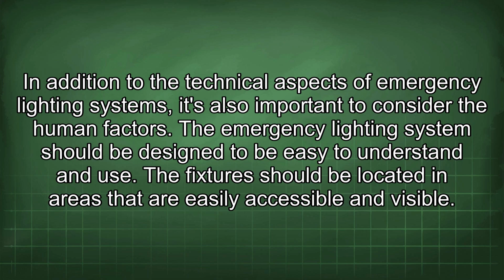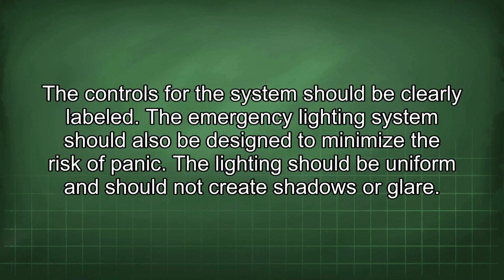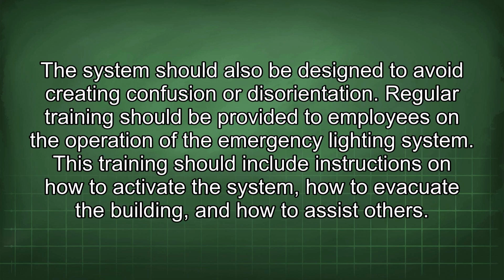In addition to the technical aspects of emergency lighting systems, it's also important to consider the human factors. The emergency lighting system should be designed to be easy to understand and use. The fixtures should be located in areas that are easily accessible and visible. The controls for the system should be clearly labeled. The emergency lighting system should also be designed to minimize the risk of panic. The lighting should be uniform and should not create shadows or glare. The system should also be designed to avoid creating confusion or disorientation.